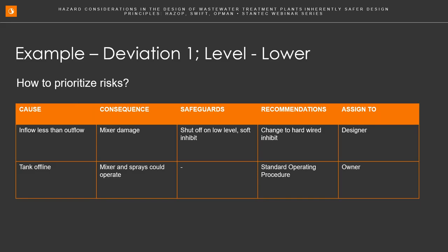The safeguards that are in the design at the moment: there is a soft inhibit through SCADA to shut off the mixer once the level approaches the blade. The team wasn't happy with that. They said, no, not good enough, we need to have a hardwire inhibit. So that was assigned to the designer to put in. Another cause is the tank is offline. If the tank's offline, the mixers and sprays could still operate if it's not properly shut down. Well, there are no safeguards for that. That's really down to operations. So the recommendation is that you need to check, and if it's not the case, there has to be a standard operating procedure on how to take a tank offline, and that was assigned to the owner.